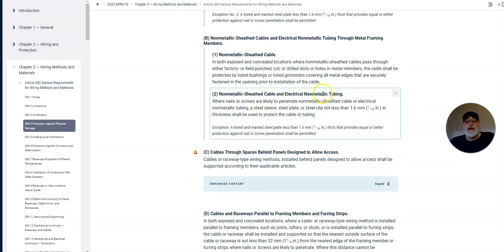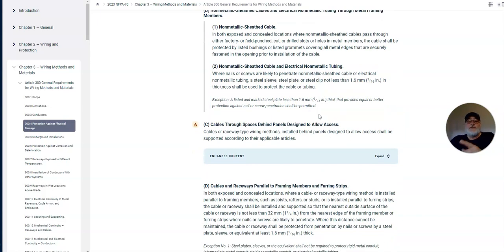Non-metallic sheath cable or EMT, or electrical non-metallic tubing, where nails and screws are likely to penetrate the non-metallic sheath cable or electrical non-metallic tubing: a steel sleeve, steel plate, or a steel clip not less than 1/16 inch thick. See, they wanted about a 16th to be able to protect the cable or the tubing. Okay, exception: listed and marked steel plate, that's the same exception we've been seeing already.